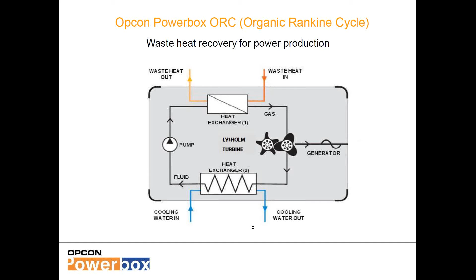And as you see on this picture, we start on 55 degrees Celsius on this waste heat as the lowest. So from 55 degrees up to 160 degrees Celsius you can utilize in this ORC version. And as you see also on the generator power, it's in three sizes: 400, 600 and 800 kilowatt. And just to give you a hint of the flows that we need for the heat, for the hot water side, it's roughly between 100 and 600 cubic meters of warm water per hour that we want to utilize. And on the cooling side, it's roughly the double amount of water, between 300 and 1,000 cubic meters per hour.